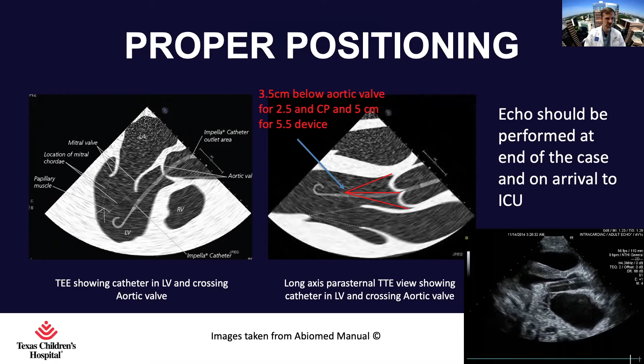We want to make sure that the catheter and the pigtail of the catheter are not impinging on the mitral valve or tangled in the mitral valve, because that can actually lead to incompetence of the mitral valve, loss of cardiac output, and decompensation in the patient. I've delineated what the true echo picture looks like with this device. Typically, you will see a shadow coming off of what we call the cage of the device, which is the metallic part of the catheter. That's where the inlet of the device starts, and that's where the measurements to the aortic valve should be performed. So the echo should be performed at the end of the case, as well as right away on arrival to the ICU, to ensure that it's still in the right position.